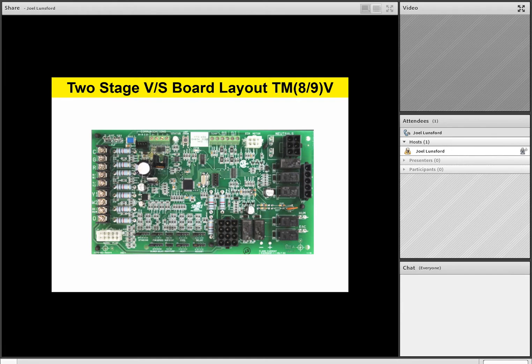Starting at the left-hand side, we have C for 24-volt common. Again, this is if you're hooking it up 24 volts. Now, it should be noted that the variable speed furnace is also communicating capable. It's communicating capable, and we'll talk about those terminals as well, but you can also hook them up 24 volt. And so, just a conventional 24 volt hookup, we're going to be using the terminal strip on the left-hand side that we're looking at right now.